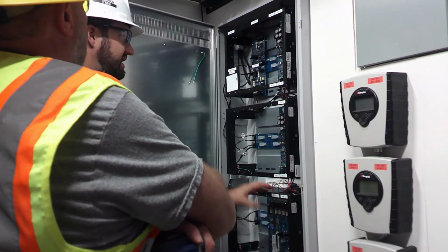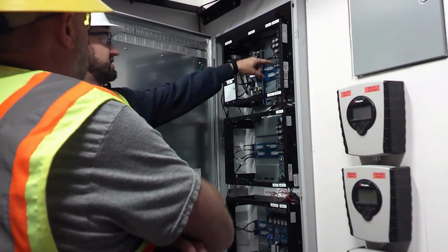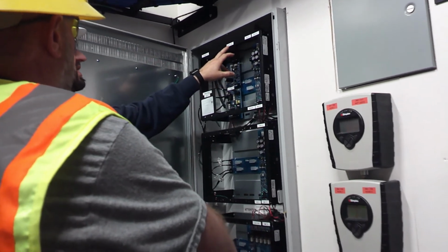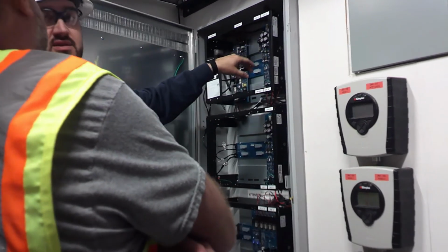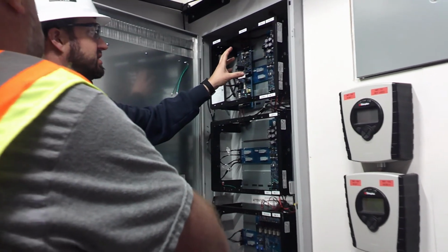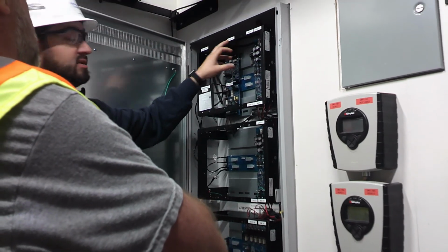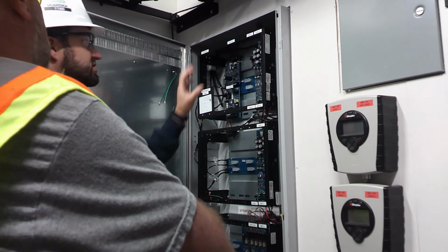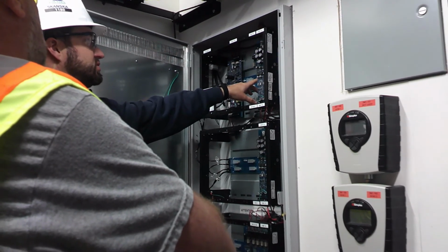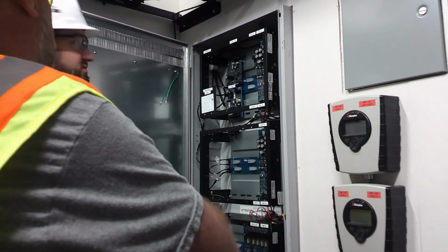For your amp, power supply, NAC card, power supply, NAC card. Here's your IDNet cards. They only have 2 loops out up top. So IDNet, here's your card address 18. If the main panel ever shows card 18, open loop trouble or something like that, and it would say building C, you would know to physically come over here, check your IDNet loop short light open, and you would know it's either A or B since C and D are unused.